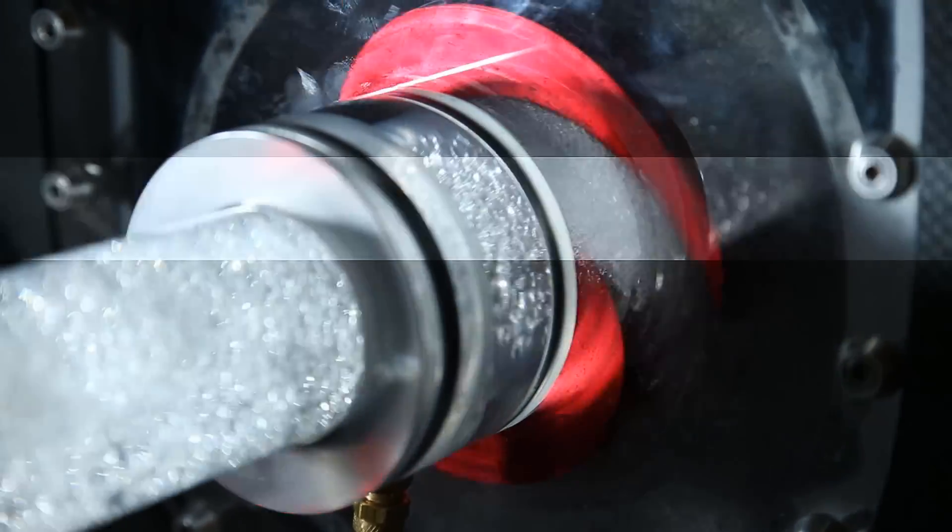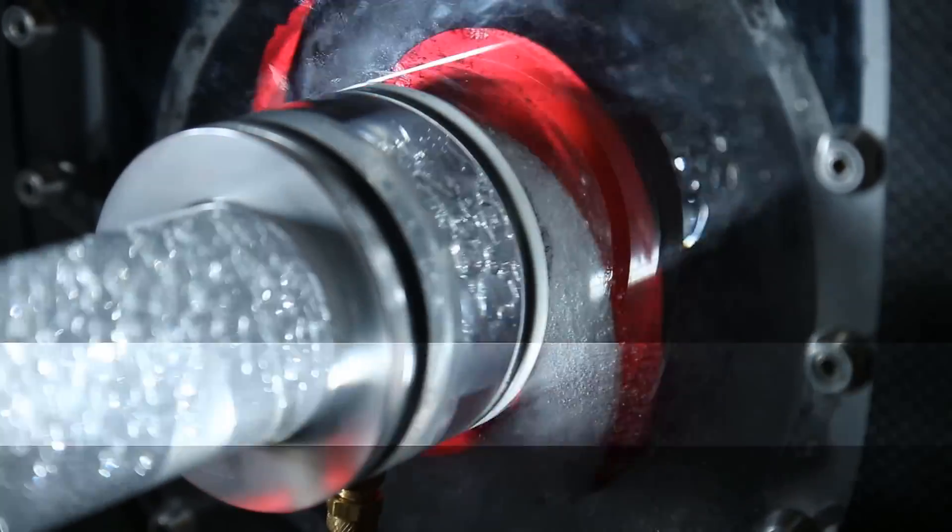If I continue to close the valve, I'll move the cavitation right in there to the eye of the impeller.